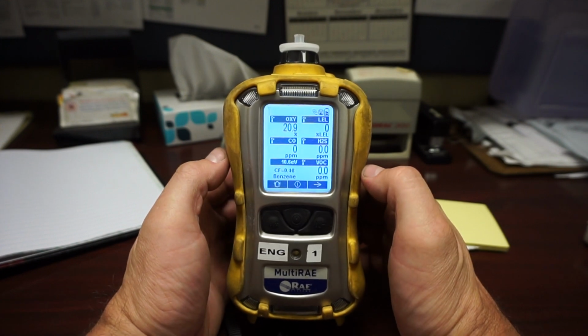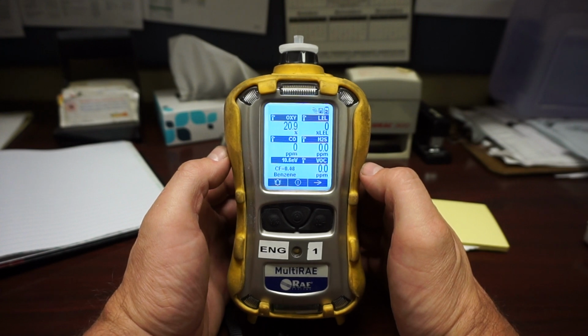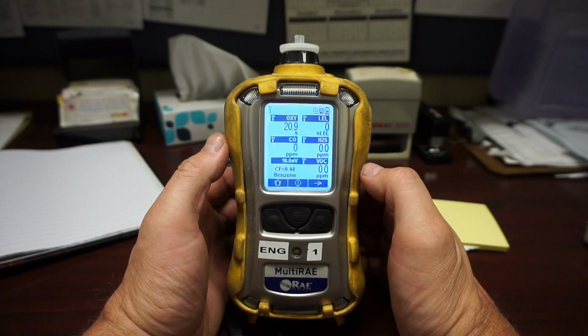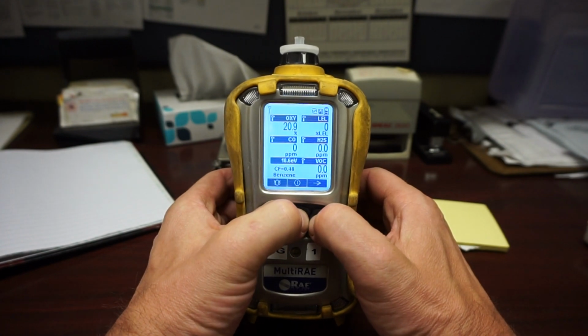So if we're looking at a benzene incident, it'll read 1-to-1 with what levels of benzene we have. Keep in mind that it is a PID VOC meter, therefore it is not identifying, it is simply telling us that something's there, but if we do have a known, we can adjust the correction factor to let it read a 1-to-1.